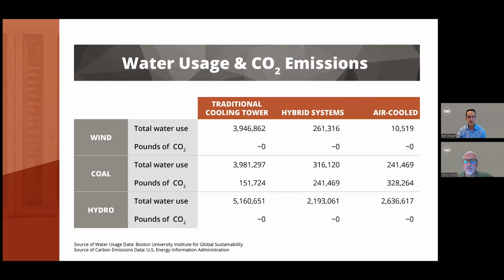Taking that a step further with the air-cooled system, again, because the water use at the data center is so high, even when I factor in the total water used to create the power, I still have a net reduction in the total water used by the system.